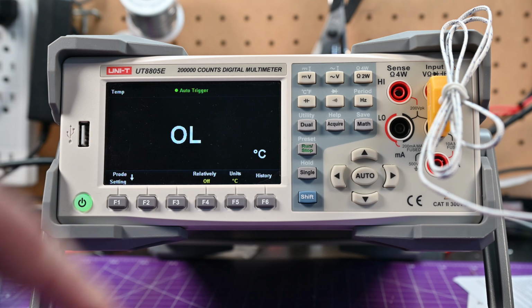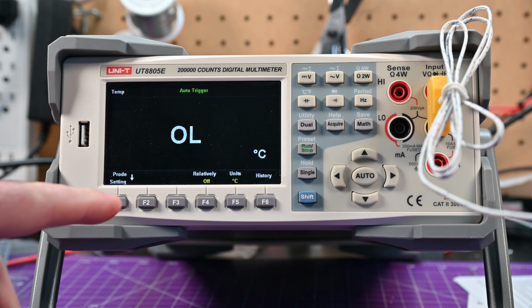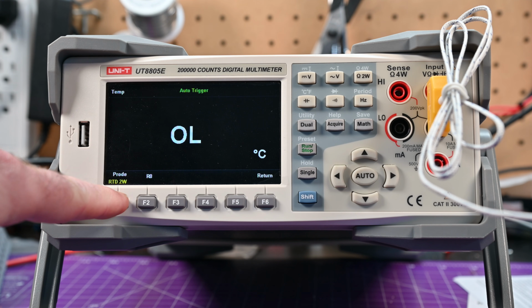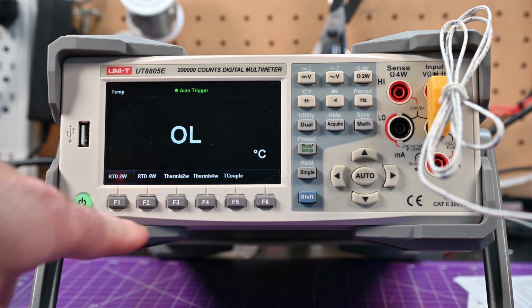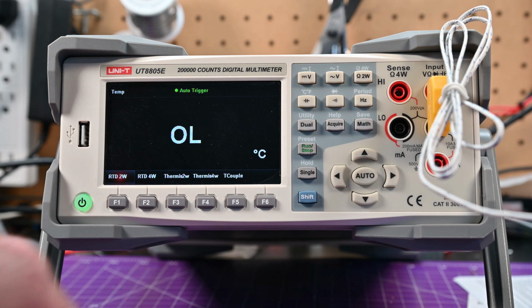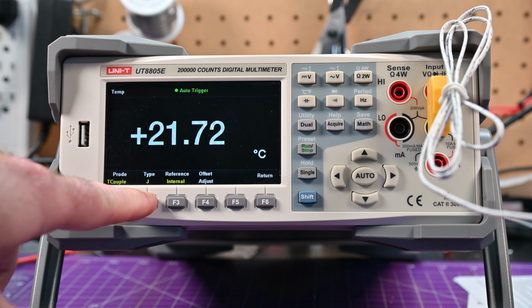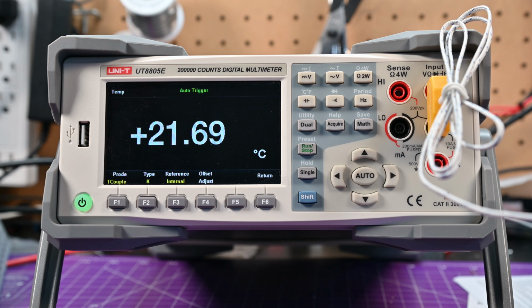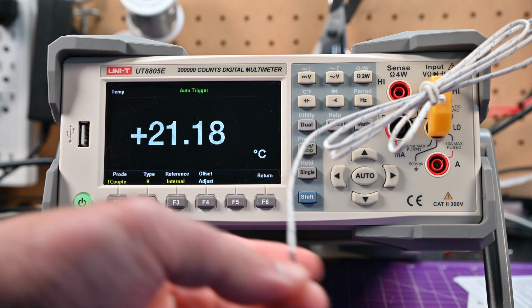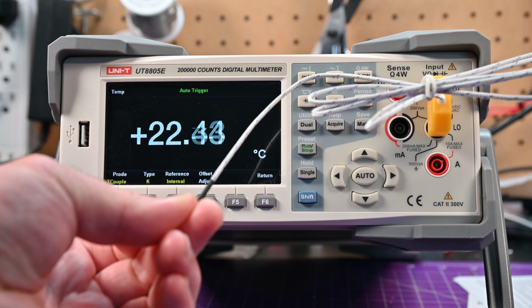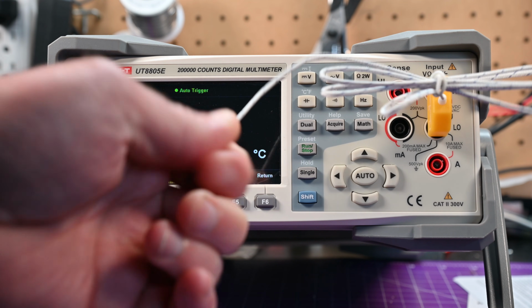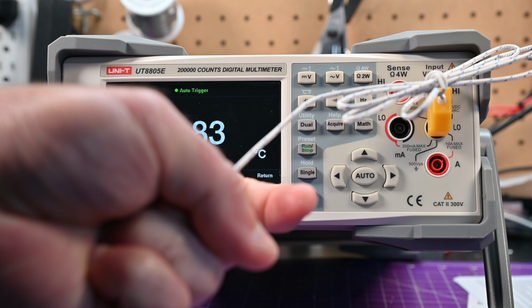If you get OL, like this one is, you have to go to your probe settings and select the probe you have. This is a thermocouple, so you have to select the type of thermocouple, which is K-type. Now you have an accurate temperature reading, and I can squeeze this and the temperature will go up, showing that my fingers are actually quite cool right now. But there we go, so this goes up.